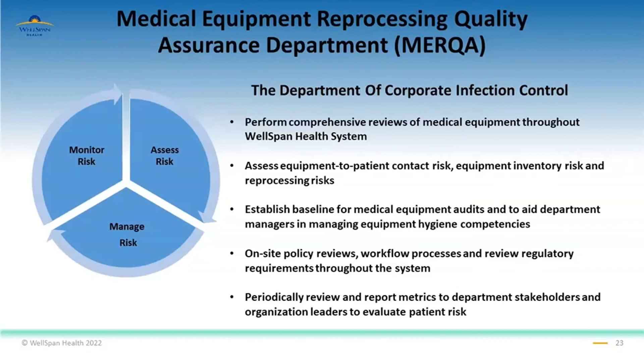Assessment of equipment risk is determined by a risk stratification scoring matrix, or the MIRA score, as I mentioned earlier. This scoring process includes, but is not limited to, the grid you see here on the screen, which is labeled risk assessment on the vertical axis, and the corresponding equipment physical risk just below the grid on the left column. Please note how these touch points are categorized. For example, if the equipment is invasive, holds water, has been recalled for safety events, or has been implicated in patient deaths or serious injury, it has our highest score of a 12.